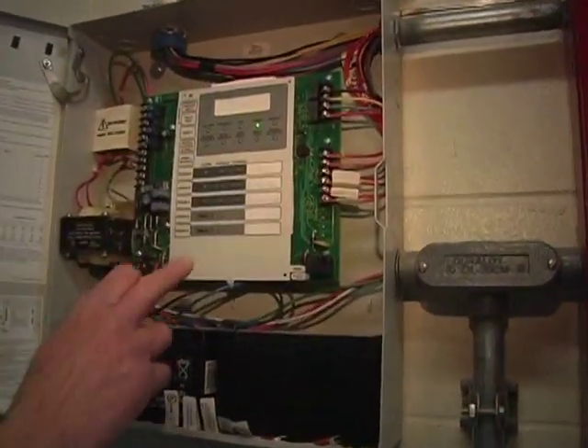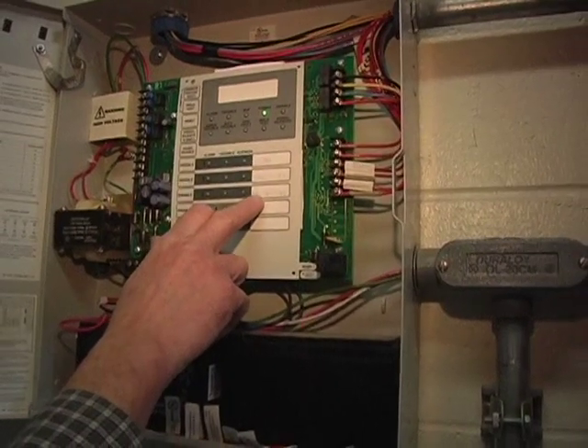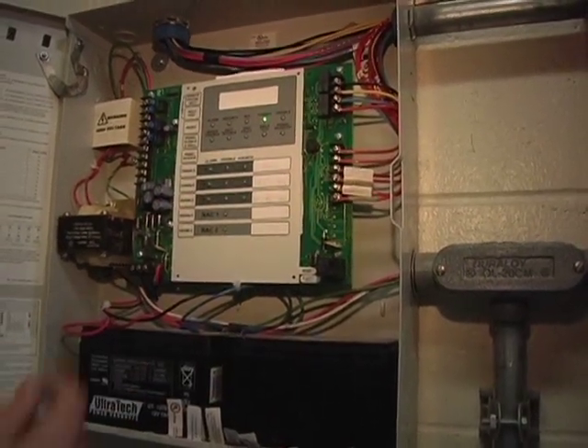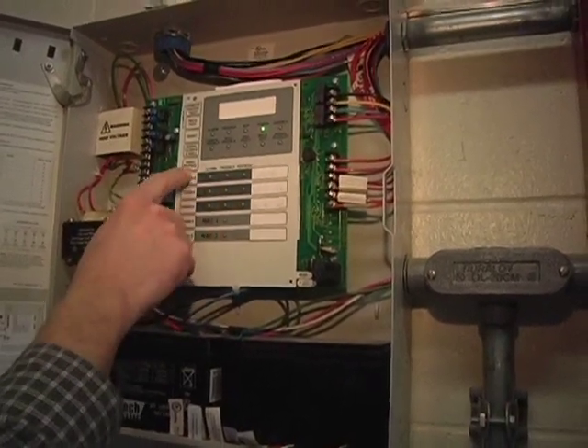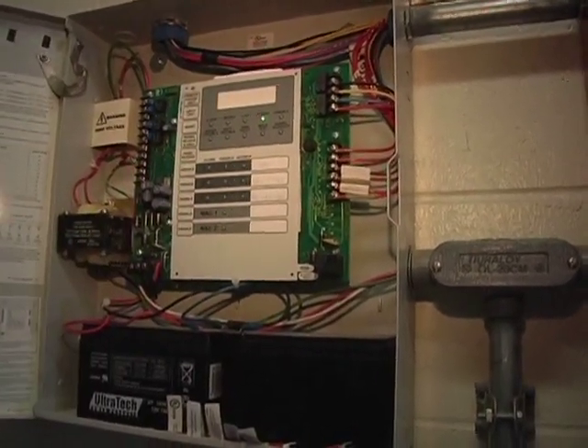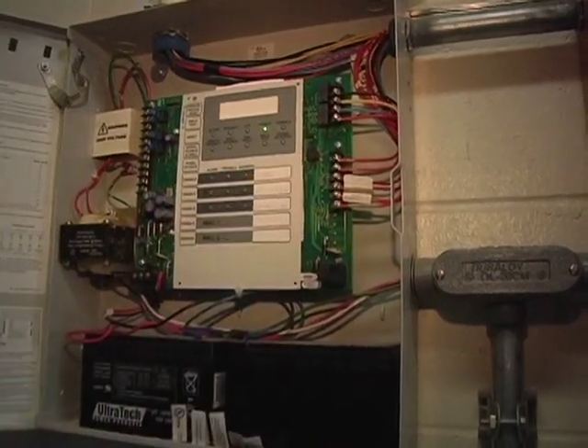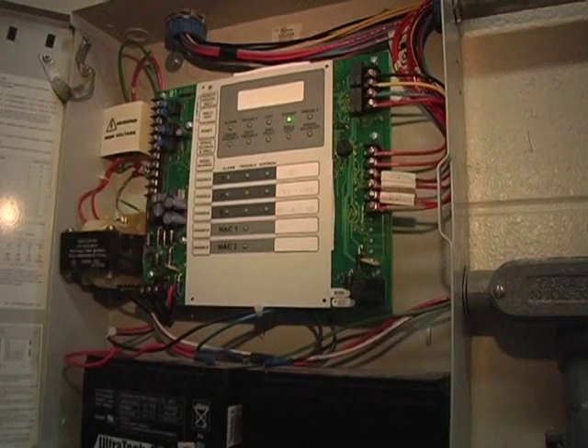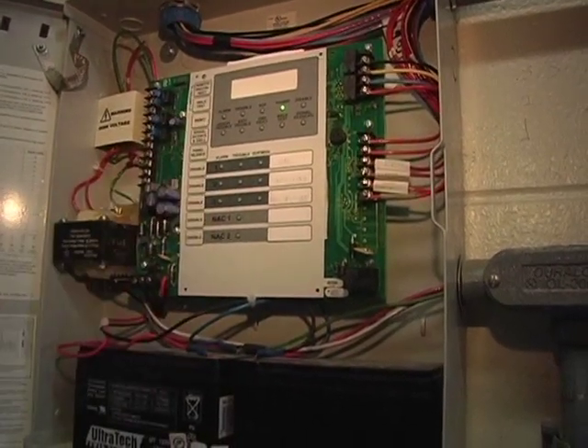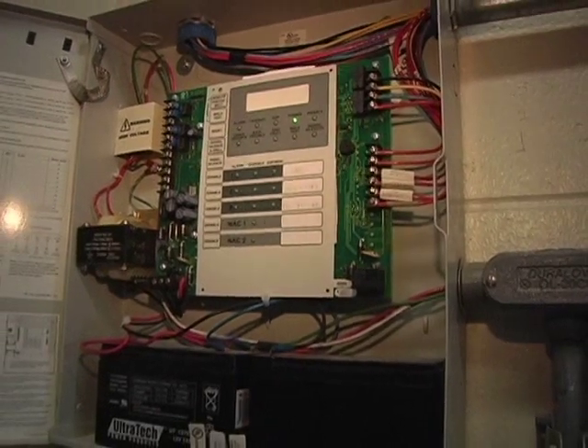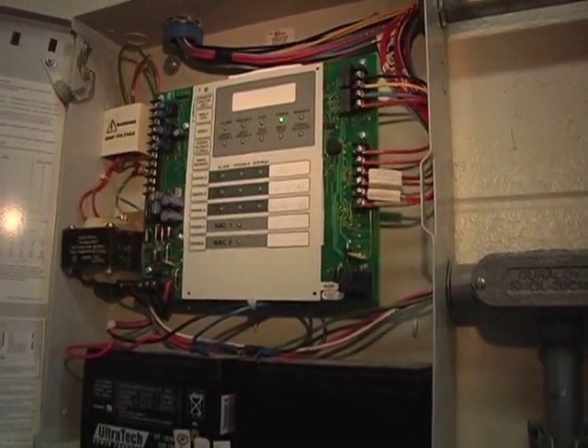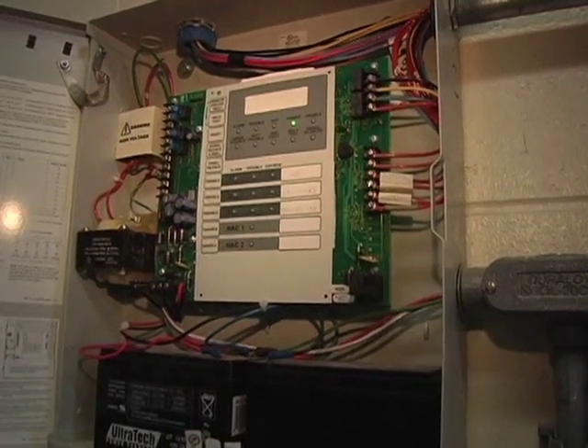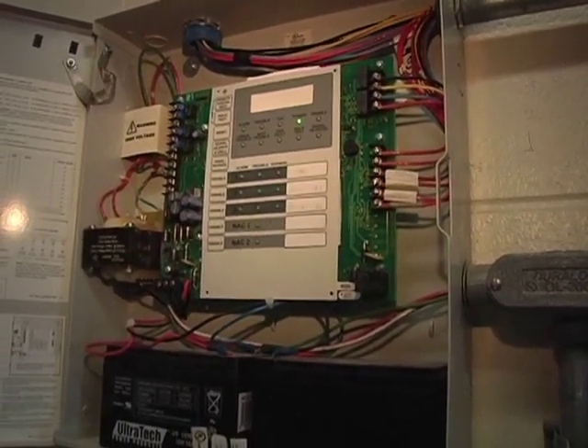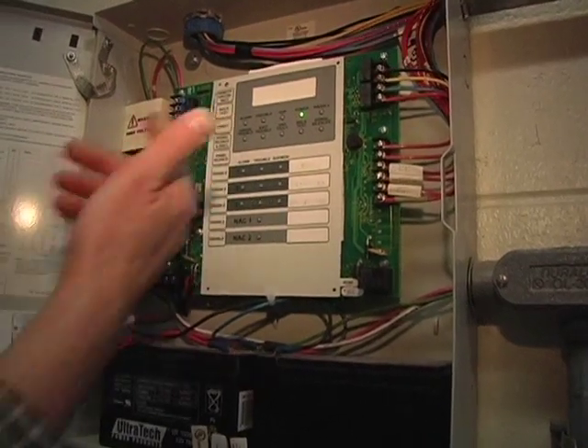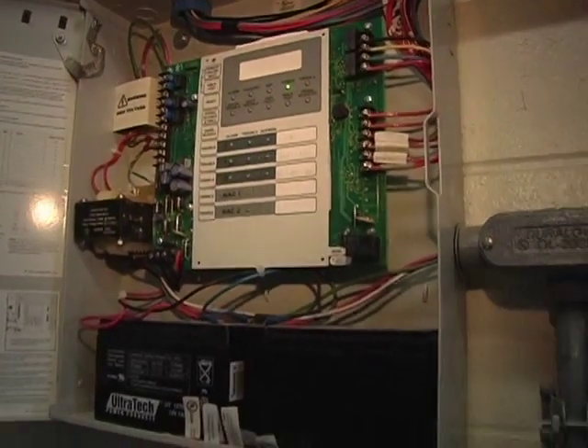Within the panel itself, it's a 3-zone panel. It's indicated on the front panel which sensors are being fed to each one of the zones. Here you have the capability, if you do go into an alarm condition, to silence the panel with the panel silence button. That will shut off the horn that's indicating an alarm condition. The reset button will reset the panel, and if the alarm was a true alarm, the device will go back into alarm and give you another alarm signal. If the alarm had been an extraneous alarm, hitting the reset will put the panel back into operation.